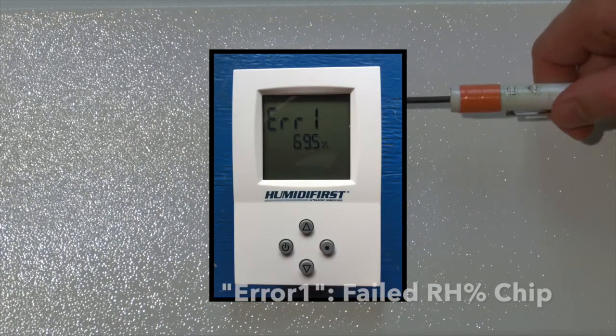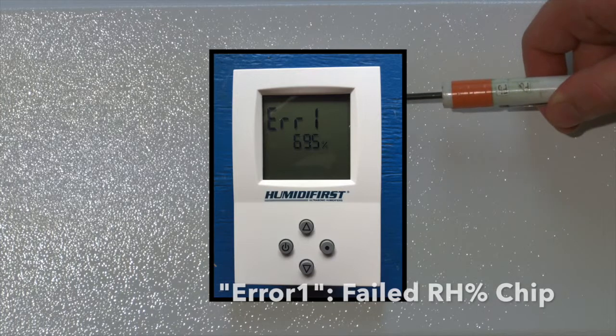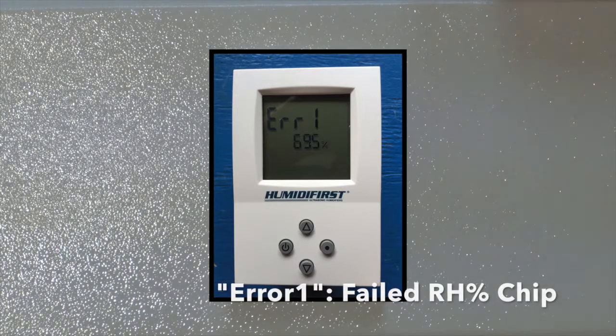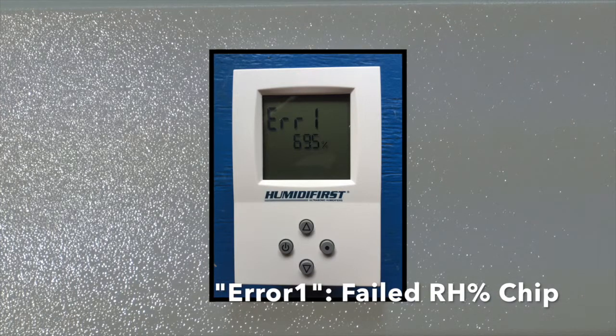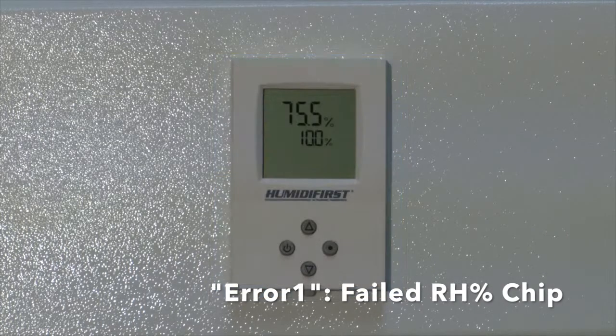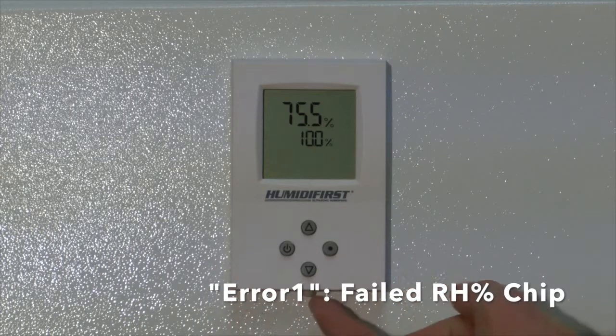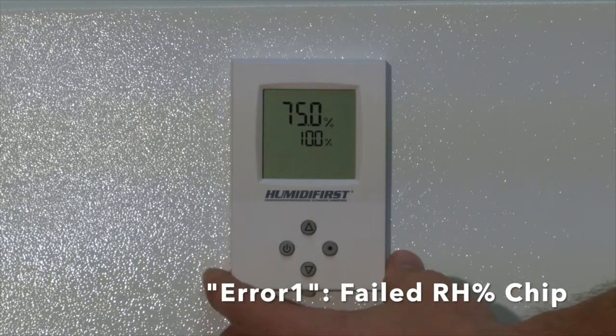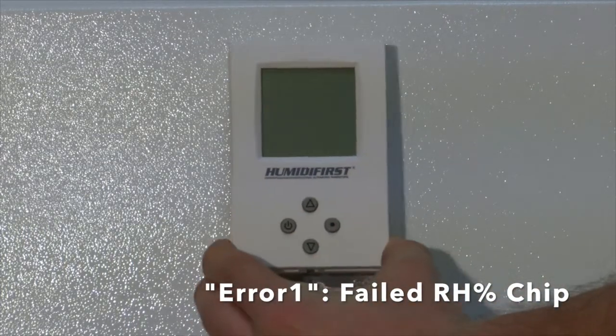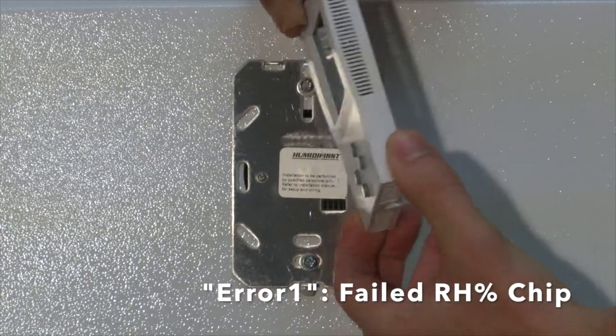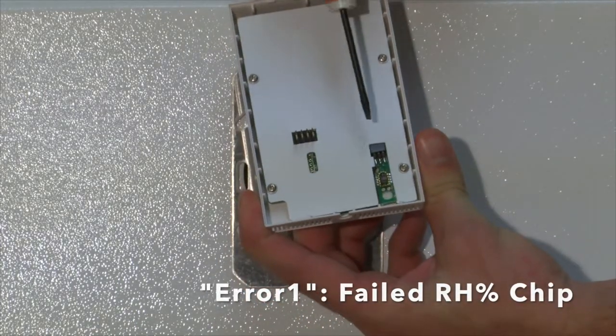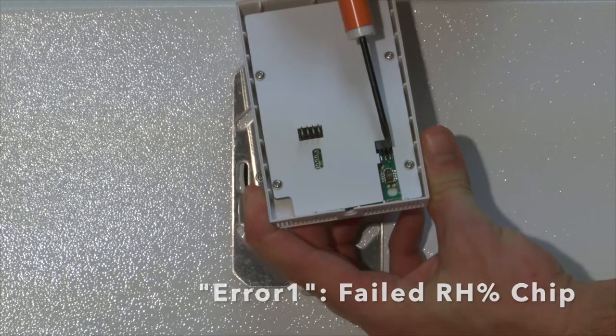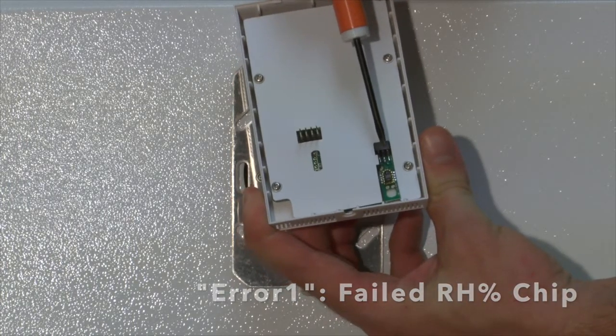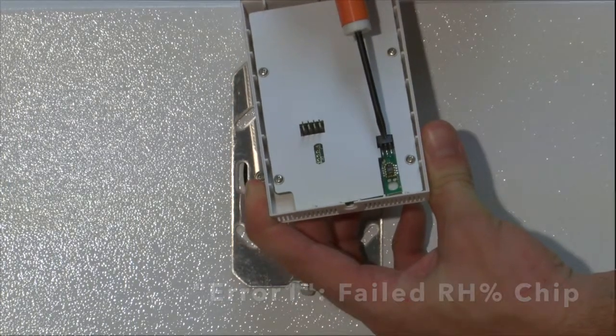If you ever see an Error 1 message in your humidity reading, this means the actual humidity sensing chip in the humidistat has failed, damaged, corroded, and is no longer useful. You can remove the small set screw at the bottom of the humidistat to remove the faceplate. You will see the humidity sensor chip in the bottom of the humidistat. This is meant to be replaceable for this scenario.